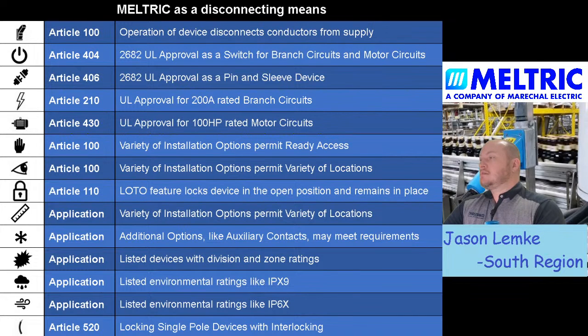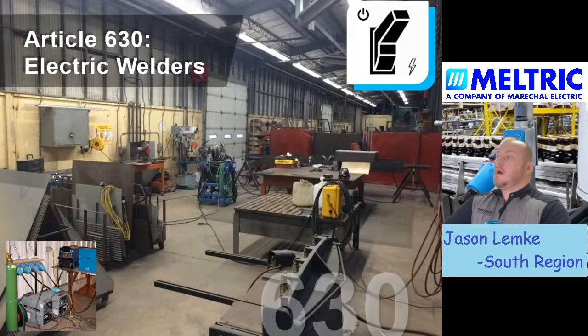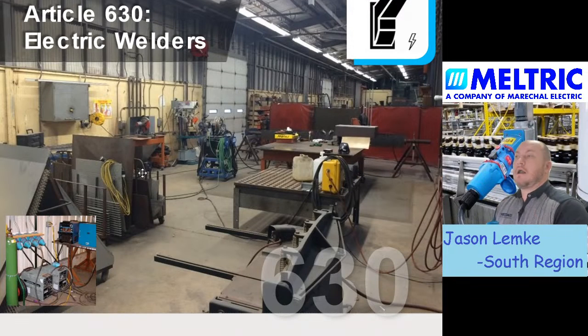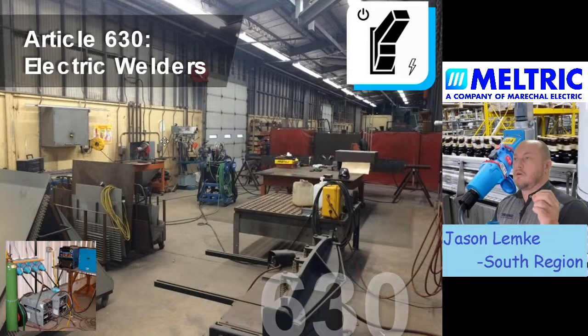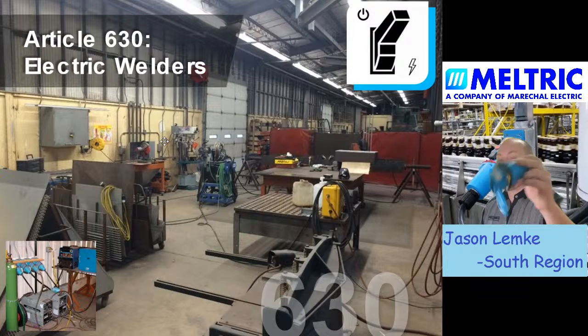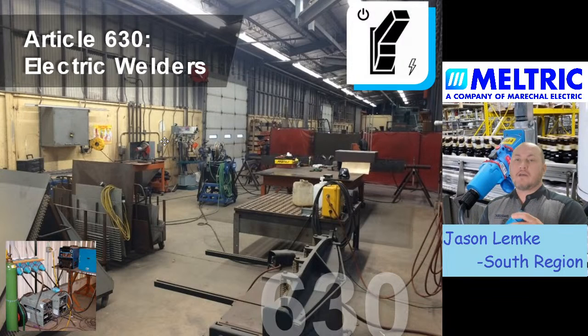Because if that is the case, for example, we'll go to welding machines, because that's one of my favorite applications. I will see things that say, all right, in the application Article 630 for electric welders, it defines that the disconnect switch or the disconnecting means must be a switch or a molded case circuit breaker. So in that particular application, if you are using a plug-in receptacle as the disconnecting means, the disconnecting means must be switch rated. So that is a requirement of the National Electric Code.